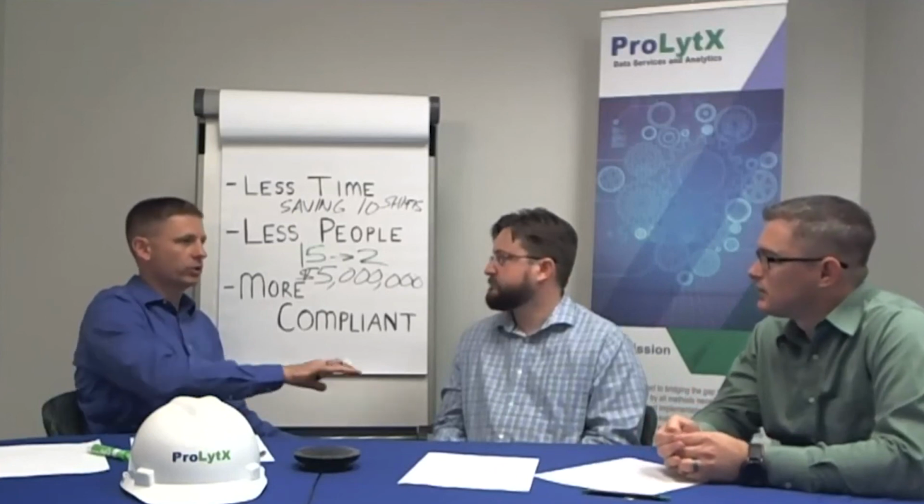Right, and this is a systematic error, which is something we catch a lot more often than I've seen anyone else catch. Systematic errors are ones where the user basically thinks it's working, but it's not designed right. So the logic is not designed right. We apply this rigorous testing scenario to it. You can find those errors a lot easier. And to be honest, we don't care how it's programmed. We just care about the results.